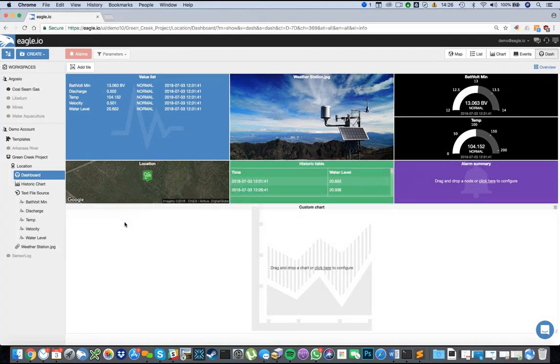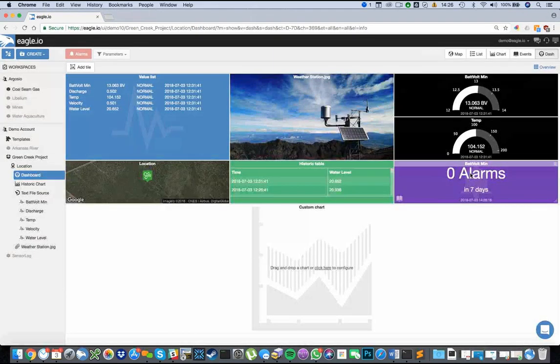And the alarm summary, if you configured up alarm all of your sensors, you would simply drag and drop the text file source onto this tile, but I've only set up alarms for the battery voltage. So let's drag and drop that on there. Of course, if an alarm is exceeded and goes off, we will get a bright red tile just here. You can't change the color of the tile to red. It's reserved strictly for alarms, okay? And orange, of course, represents someone has acknowledged the alarm.